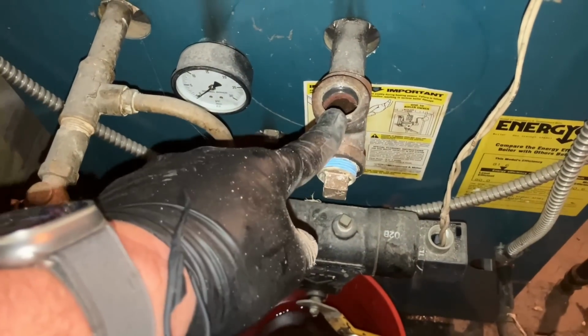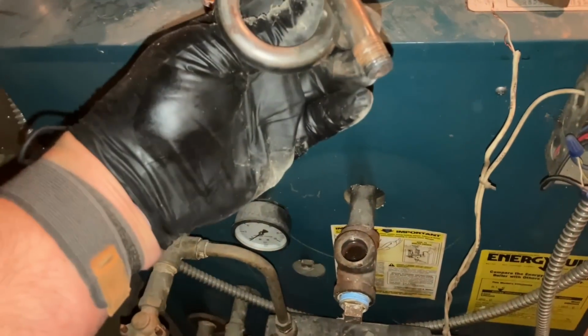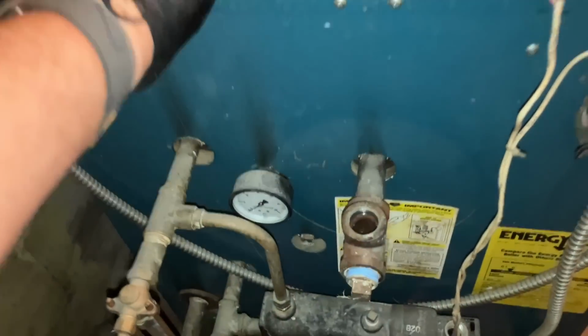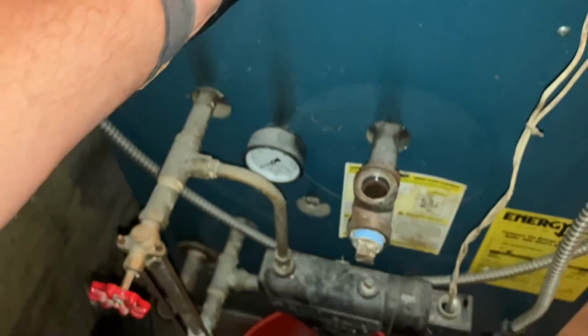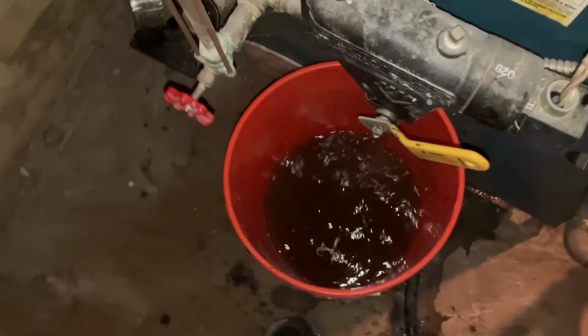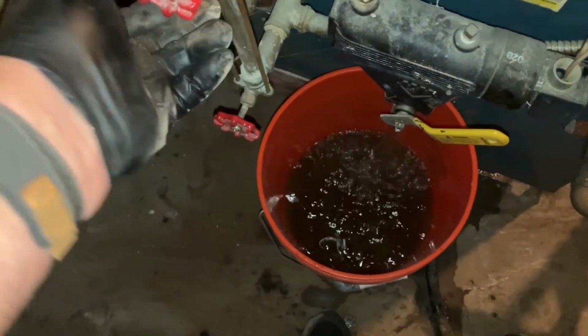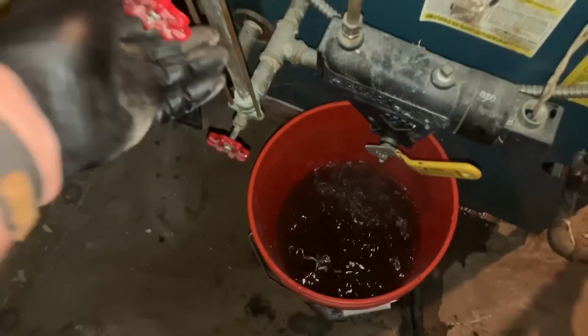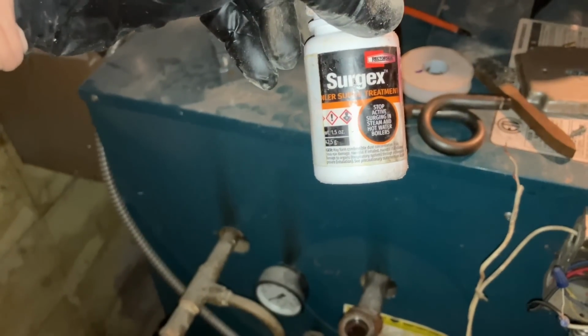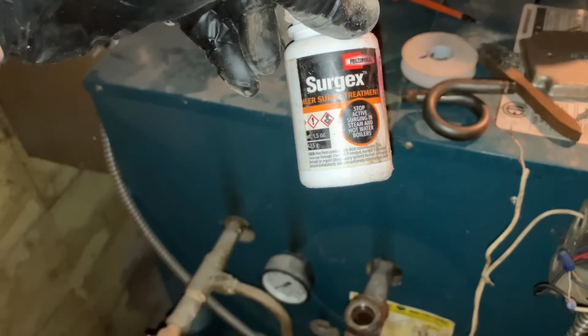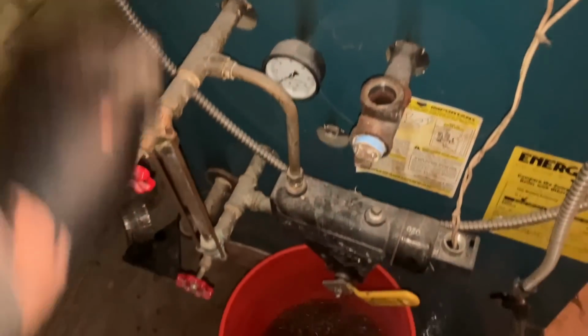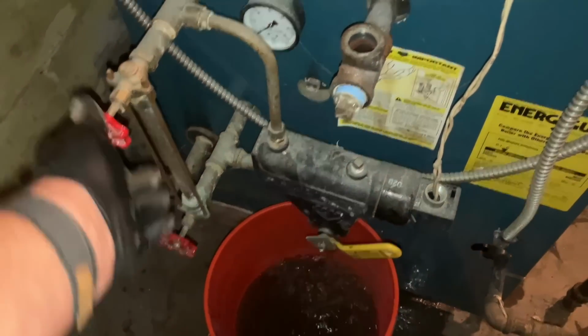All right, I removed that reducing bushing here where the pigtail and the pressure control goes. We're going to flush out the remaining caulking that's in there, and we're going to throw some Rector Seal in here. But before, let's just open up our drain. We're going to drain down the rest of the boiler, and that way we'll have a nice clean start when we add the Surgex, which is great for boilers that are surging, but it also helps promote drier steam.